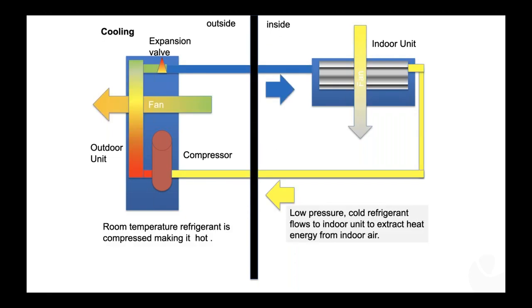Next slide. The cooling season is the exact opposite. There's a four-way valve inside of the outdoor unit. When you push the mode button and select cooling on the heat pump, it switches that four-way valve and reverses the flow so that it extracts heat energy from your indoor air. So your indoor air at 70 degrees will flow in past a coil that's cooled to something like 40 degrees Fahrenheit and extract the heat energy, pouring colder air out into the room and taking that warmer refrigerant, now 70 or 80 degrees, depending on your room temperature, out to the compressor, where the compressor compresses that gas into a higher density and really, really hot, and then blows that heat energy out into your backyard and across your bushes.